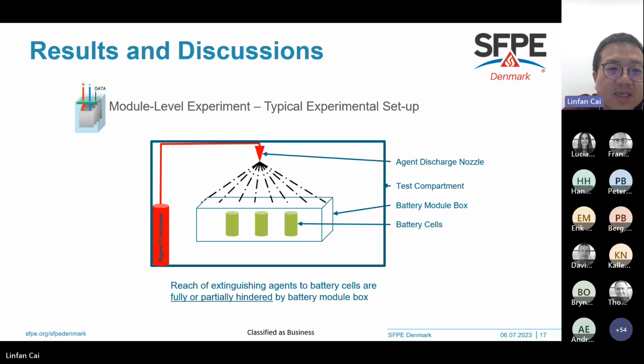For the module level experiment, this is the typical setup: the battery cells are housed within a battery module box, and the extinguishing agent is applied over the module box without direct reach to the cells inside. Once discharged, the extinguishing agent is inevitably blocked by the module box, so the degree of penetration largely depends on the ingress protection rating of the module box.